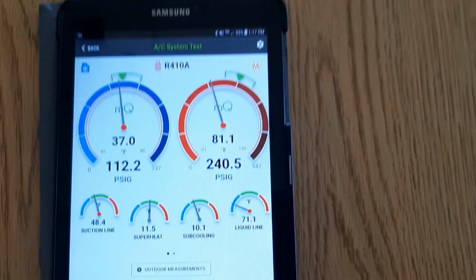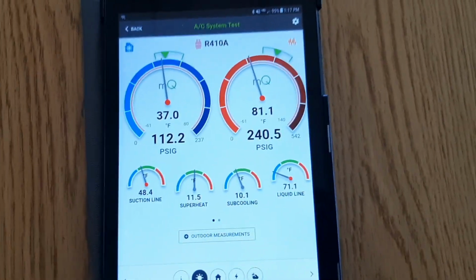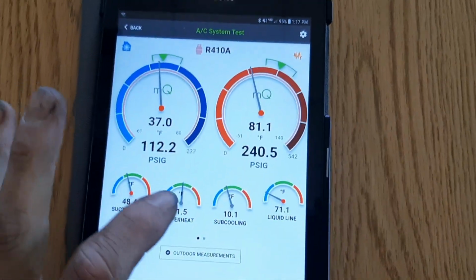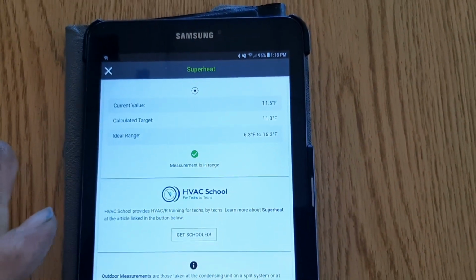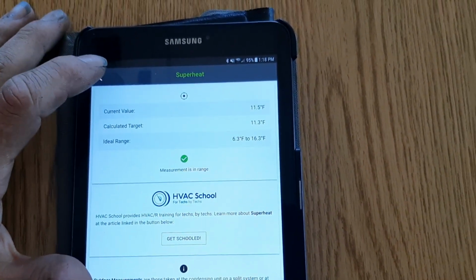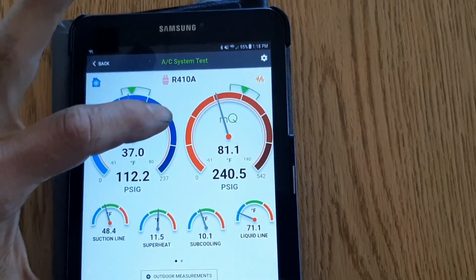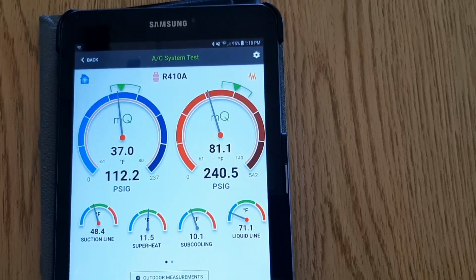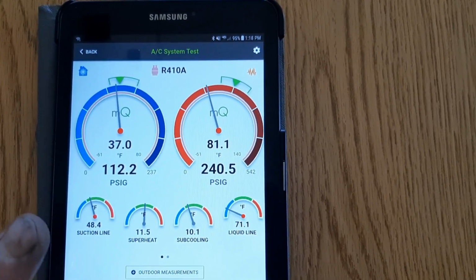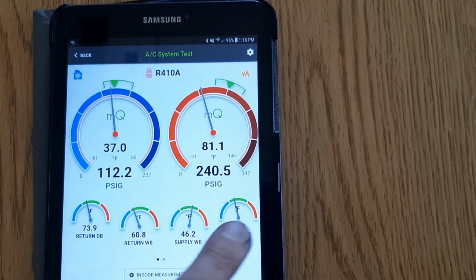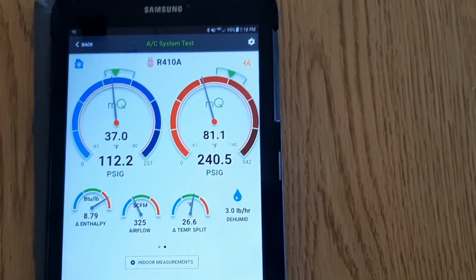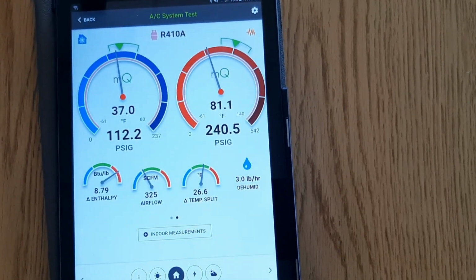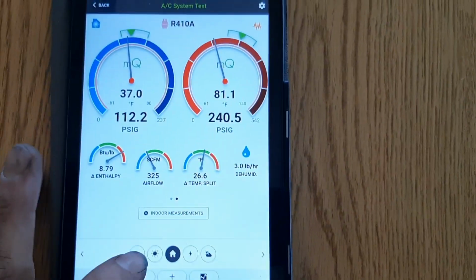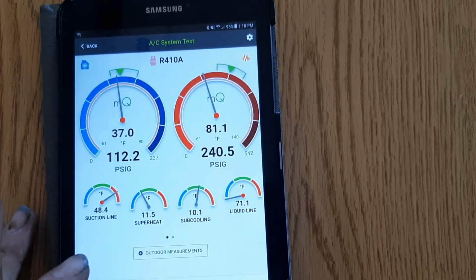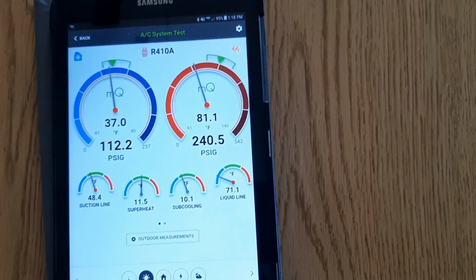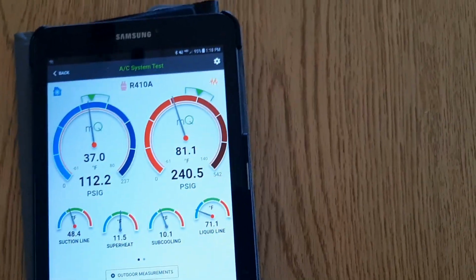So it's looking about as good as it's gonna look. Superheat did drop. Let's see what my calculated is, 11. So I mean, I'm right on as far as the superheat goes. Head pressure's climbing as my coil dries out, and I'm not in the best spot. Still got a high temp drop, but it's been sitting at that 26 mark. So it's close enough with where my probe is. That's probably going to read off anyways, because I'm right on top of that coil. But this one's doing about as good as it can.